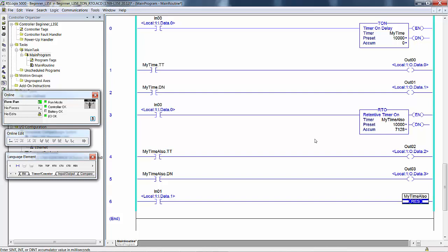In other words, you want to do something after it's been on for 90 minutes, but not 90 continuous minutes. The 90 minutes might be spread over 2 or 3 days. But when 90 minutes have accumulated, whether it's emptying a tank or lubrication on a shaft, whatever, you want to accumulate the actual runtime.